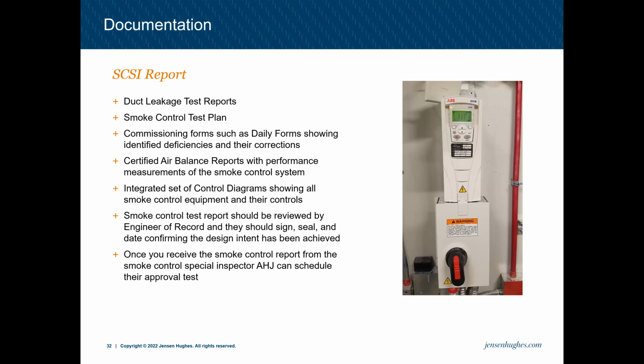With smoke control special inspection, they do have to file a smoke control special inspection report. That report is really a summation of the work being done. That will include the duct leakage test reports and the smoke control test plan. The test plan is a great document that can ensure concurrency between the construction groups, and that is the construction manager or general contractor, along with the fire alarm programmer and mechanical contractor. So everyone's aware of what systems will be tested and how they will be tested.